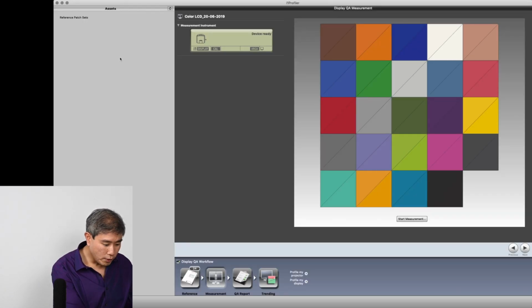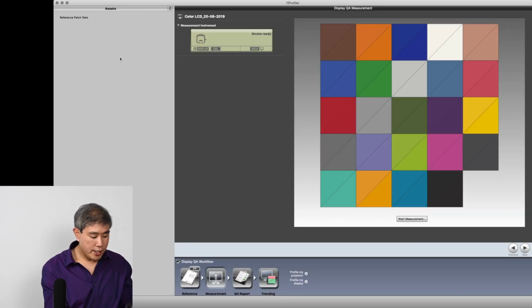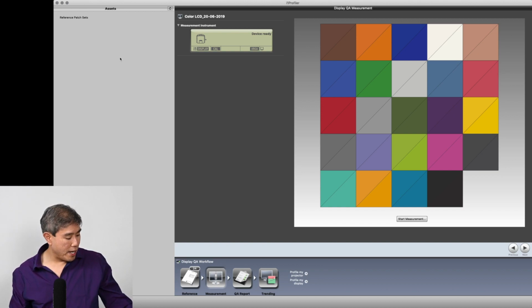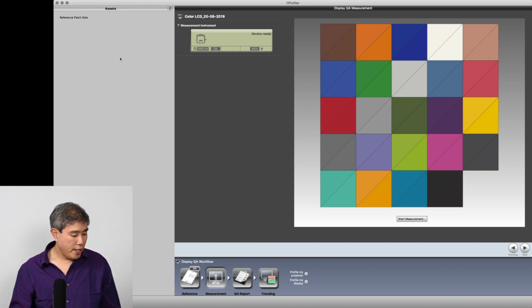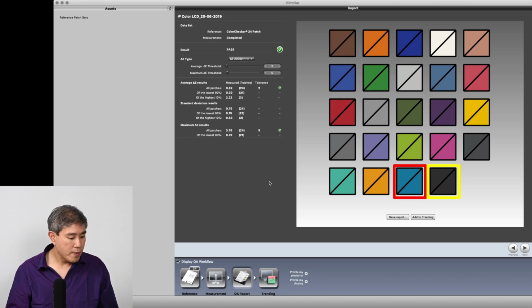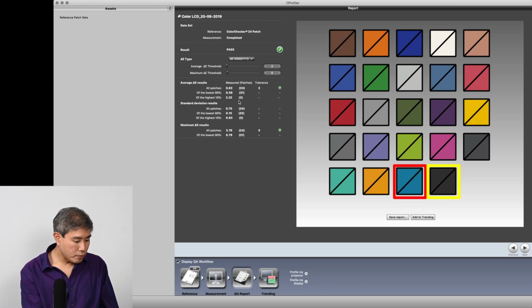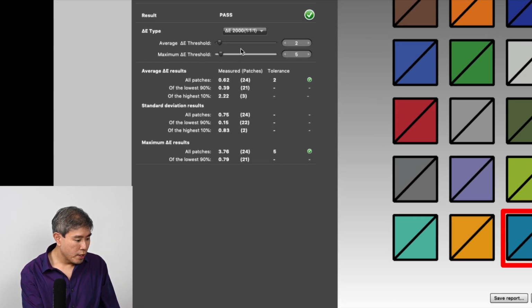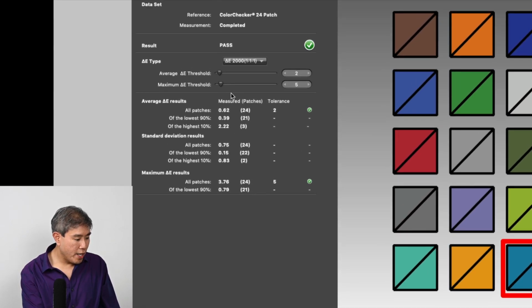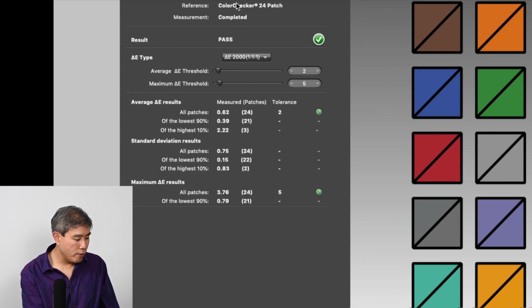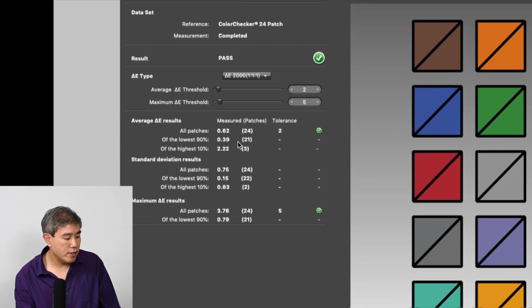Then once this is done, there we go. Once this is done, we'll take this off, rotate the cover back on again, set this on the table. And now what we can do is go into the next box down here under Display QA Workflow and click on QA Report. So in the QA report here, we get a couple of values that we can see. I'm going to go ahead and zoom in here. And we have a couple, like I said, we have a couple of values. The result right now is showing, again, pass, which is actually not bad.